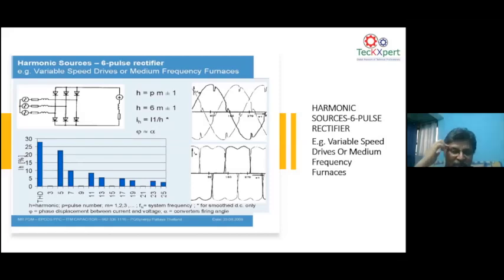The higher order harmonics, sometimes if you go with a harmonic analyzer which can measure only up to the 50th order harmonic, naturally are not seen by the harmonic analyzer. So sometimes you will say the active front-end drive is not producing harmonics, but in reality, it is producing harmonics from the 63rd and above. When I say 63rd, it will be at 3000 hertz, 4000 hertz, like that. But your harmonic analyzer, since it's only measuring up to 2500 hertz, says there's no harmonic. So you have to be very careful when you consider active front-end drives as a replacement for normal drives for reduction of harmonics.